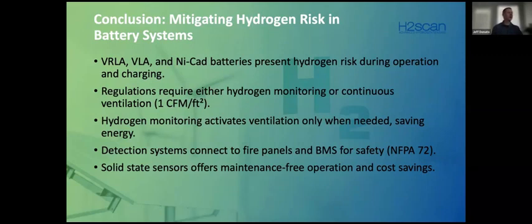The regulations do require either monitoring or continuous ventilation. So you either provide the continuous ventilation according to the standard, which is the IEEE 1635, or you add the monitoring, and then you can have the monitoring activate the fan. That will eliminate the need for continuous ventilation. And then, of course, as I mentioned before, make sure the detection systems connect to either fire panels, a battery monitoring system, a building management system, or a SCADA system. Make sure it alarms somewhere other than just an audible alarm in the room.